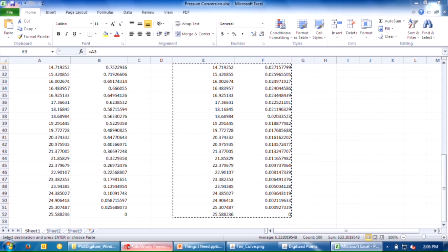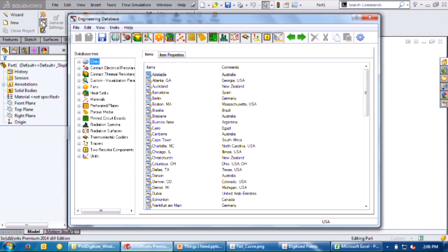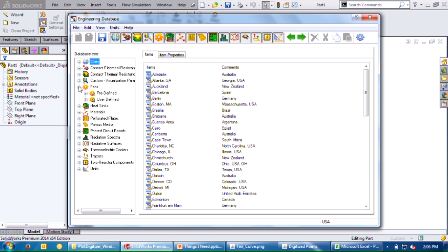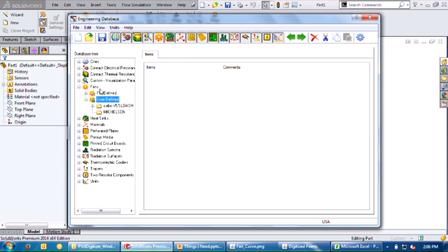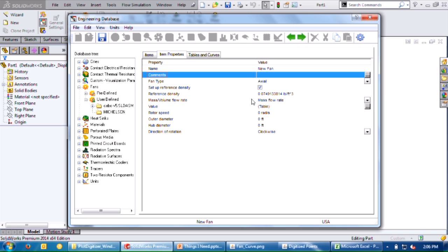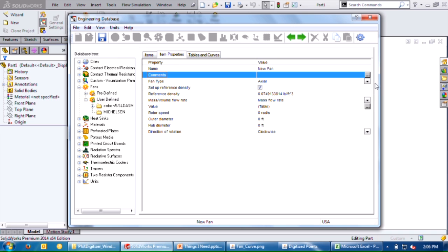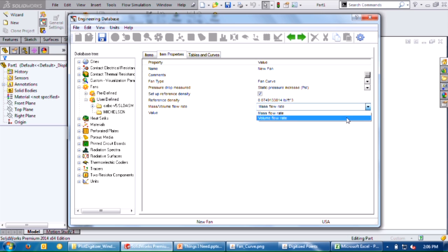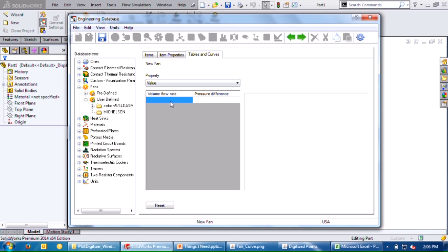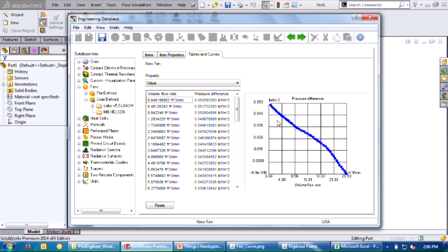I'll go over to SOLIDWORKS and into my engineering database. I'm going to create a new fan. Go into the user defined section and create a new fan based on volume flow rate. Then I'll go to my table and simply control V or paste everything. And we have our curve from a PDF to flow simulation.